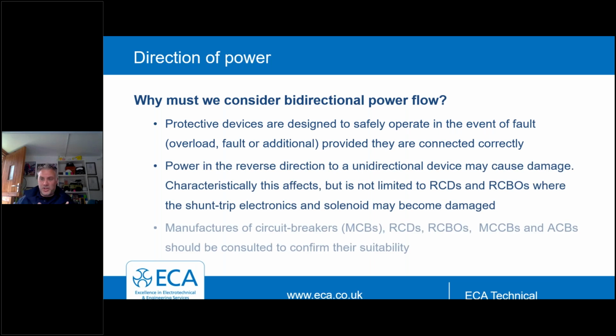So why must we consider power flow? We've just touched on this, but they're designed to safely operate in the event of a fault. So they may have reduced capacity if they're wired incorrectly. We've heard recently that if devices aren't wired up correctly, it may affect some devices with their shunt, their tripping circuit, because there's some electronics involved in that, and we don't really want to damage that. So that's why the regulations are coming out to be changed in Amendment 3, to let you know, let's use the right device here.